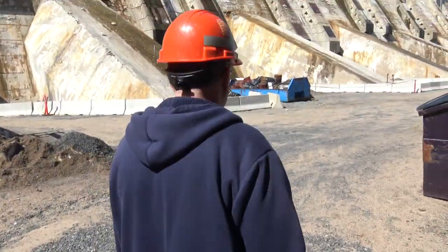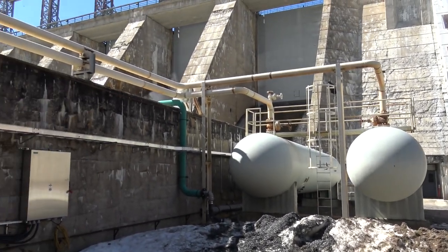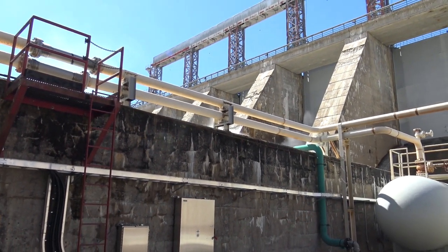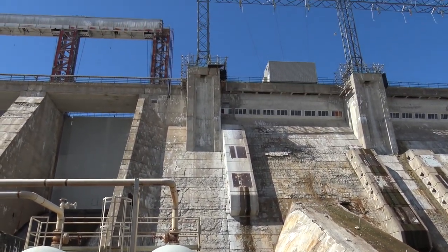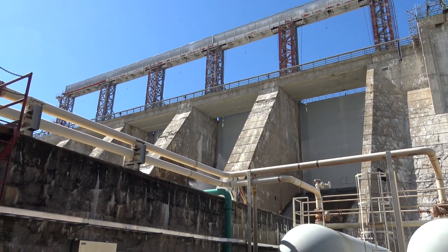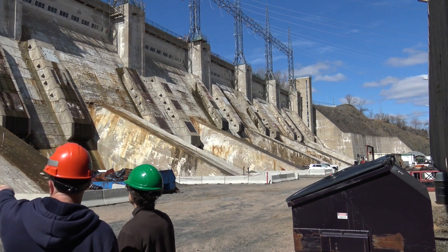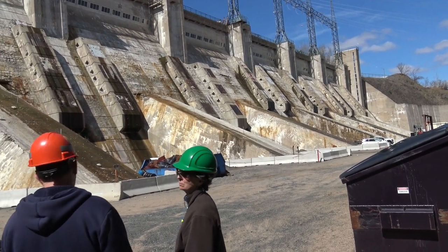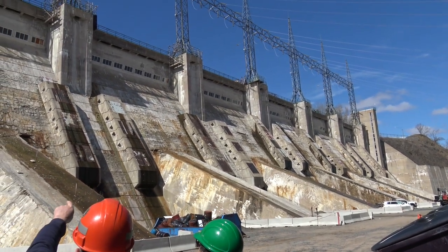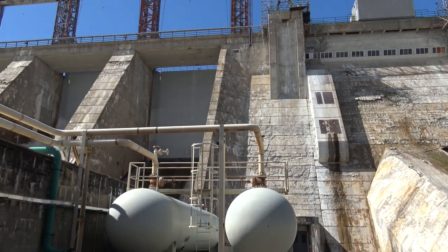This would not be fun to walk around in. So there are your spill gates — gate number nine here has a little bit coming out. This is gate number 10 right here. They don't open that unless they absolutely have to, because the water sprays all over the place. They'll open this gate only if they need to. You notice the concrete face here is getting bad — there are even chunks of concrete on the structure. They've got Jersey barriers set up so people don't go near there in case a piece comes off. This summer they've got pallets of mining screen — they're going to drill and screen and pin all these places so if anything falls off, it stays contained, just like in a mine or on the side of the highway.